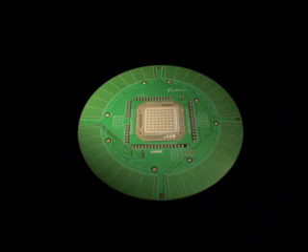The probe card has needles on one side matching the pattern of the devices on the wafer, and terminals on the other side which match the contacts on the tester electronics. This provides the electrical contact from the wafer to the tester.